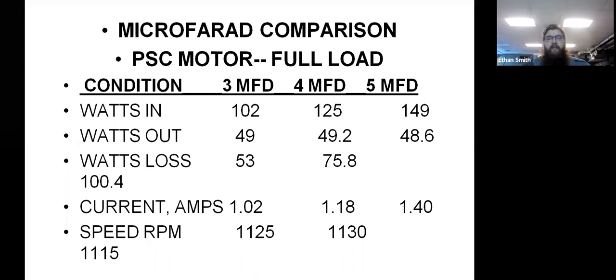Okay. I would agree, because you're losing efficiency. Even in the 4, there's not a significant RPM gain. Okay, so this motor is actually spec'd for a 3 microfarad capacitor. But just going up 1 microfarad, we get almost a 50% increase in efficiency loss. You go up 2 microfarads up to a 5 microfarad, and you've got a 100% decrease in your motor efficiency, with no appreciable gain in RPM, running amperage, anything like that in the positive direction.